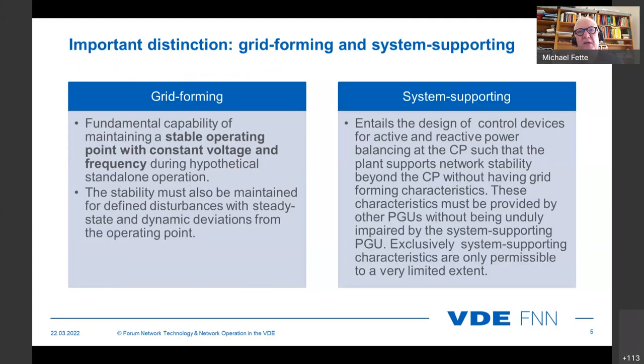Very brief in the definition. Under grid forming, we discuss the fundamental capability of maintaining a stable operating point with constant voltage and frequency during a hypothetical standalone operation. Stability must also be maintained under defined disturbances, with steady state and dynamic deviations from the operating point. That simply means we have controllers inside which can deal with the conditions.